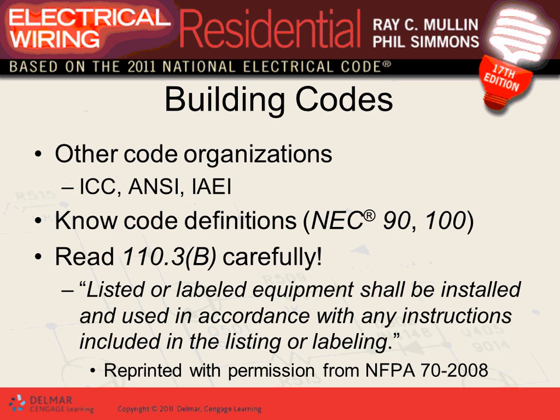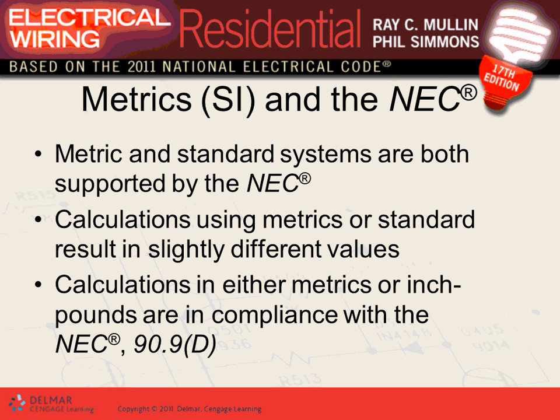Simple example: take a panel listed and labeled for indoor installation and put it outdoors in a parking lot—now you've violated its listing and labeling. This comes from UL. A fixture might be listed for use in a dry location; can you put it outside and still maintain its listing? No. That's how an inspector can catch you, even if it's not explicitly in the NEC code book. If the listing and labeling doesn't allow the equipment to be used in a location, you'll get nailed for it. So pay close attention to listing and labeling for equipment.